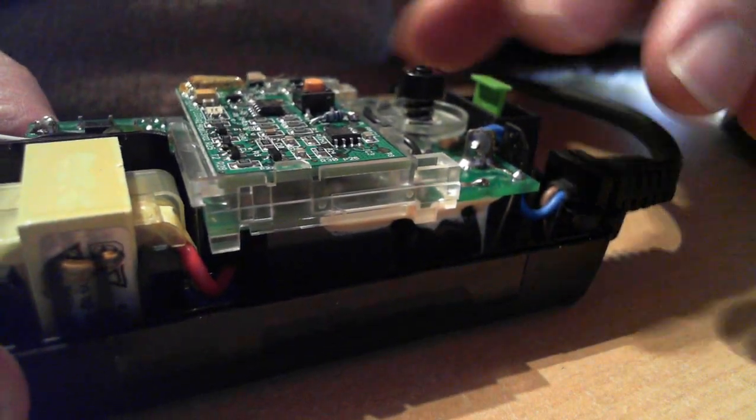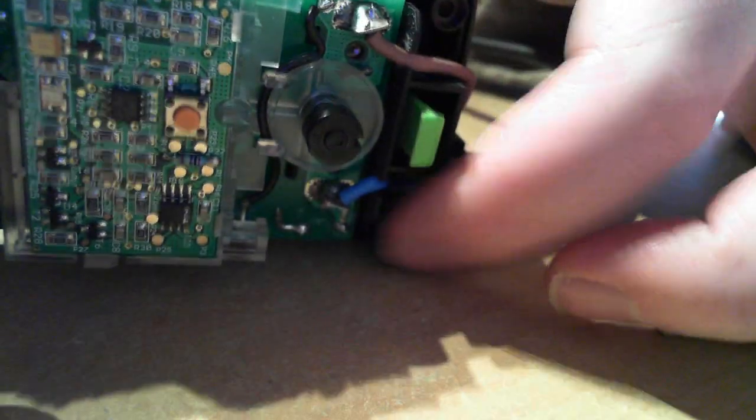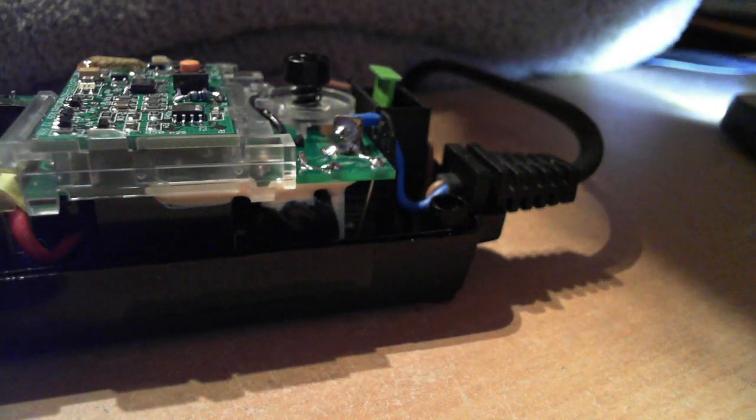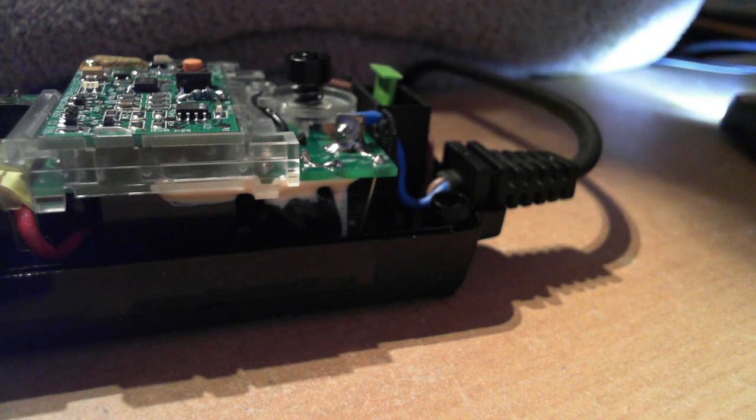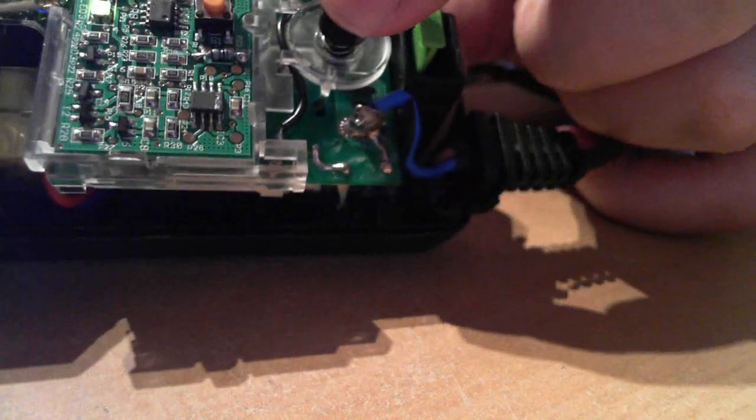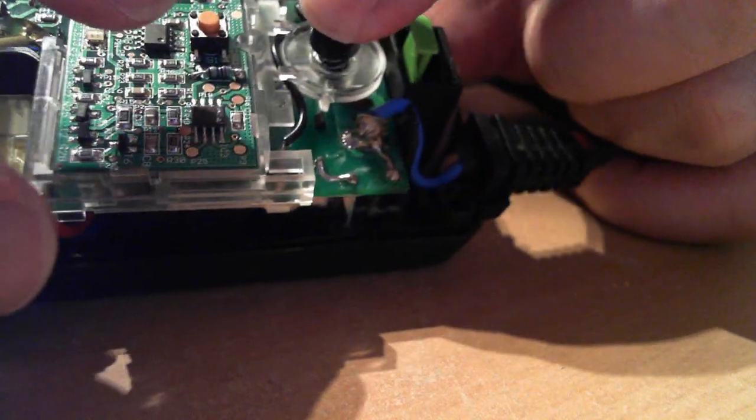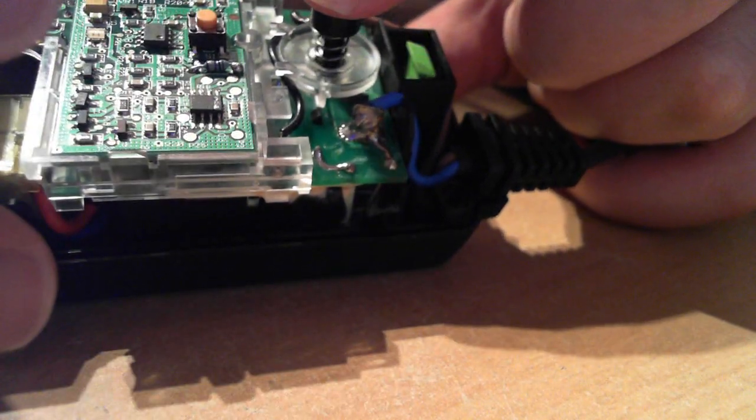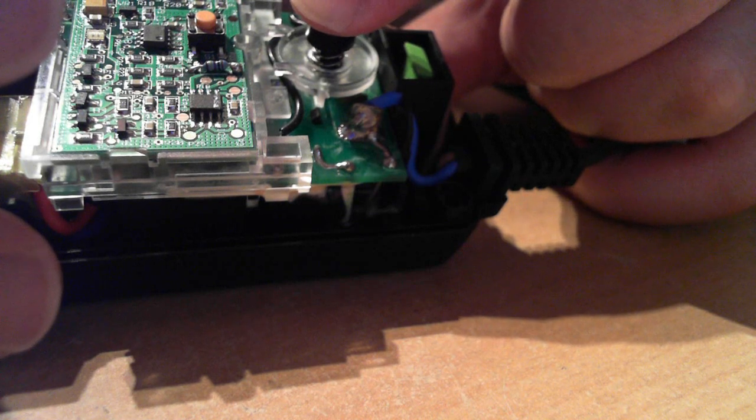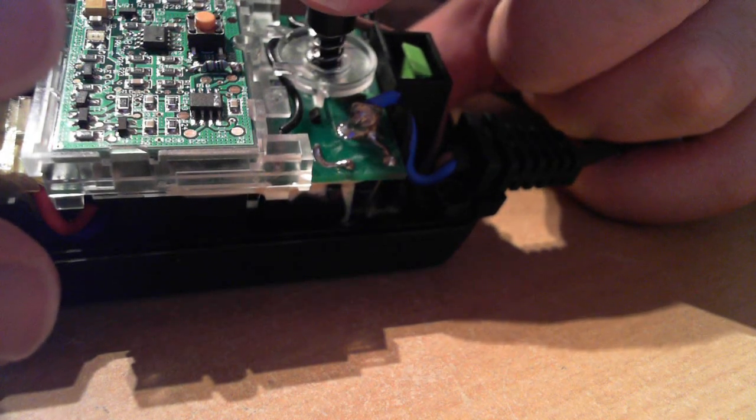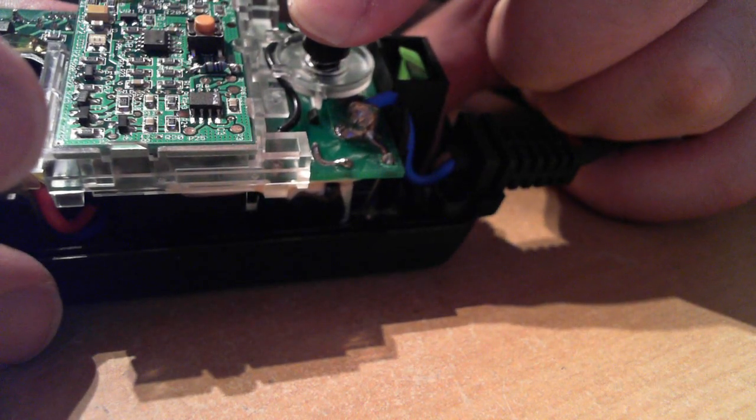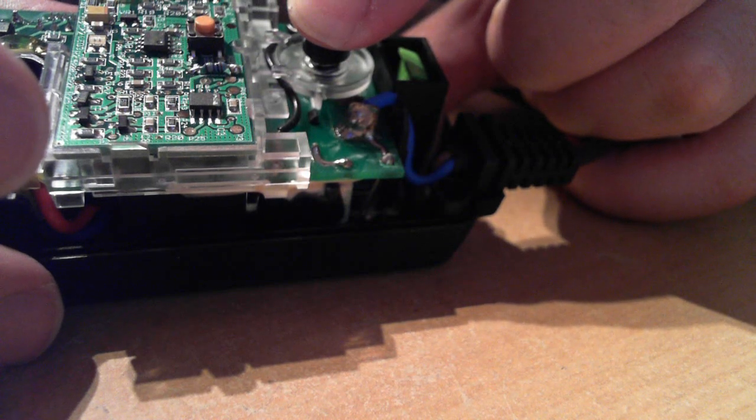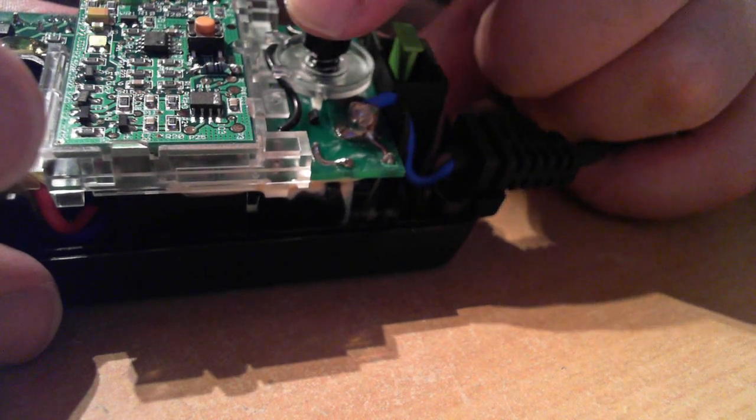Now then, keeping your fingers clear of the mains terminals. Do not touch these mains terminals at all. Whatever you do. I don't want to teach young eyes to work on live equipment. That's for sure. So keep your finger over the top of this button, but well away from the mains terminals. Push this pin in. Trip it by pressing the test button here. And it fires up. The solenoid releases. Releases the pin. The pin under spring pressure goes up. And the trip is off. Reset it. Push the pin in. The barb catches on the solenoid plate. The plate the solenoid engages into. Pulls the contact shut. And we're back on again.